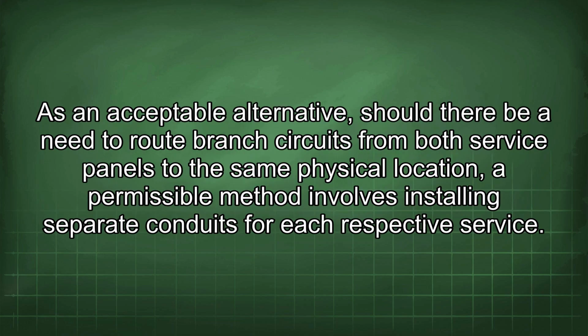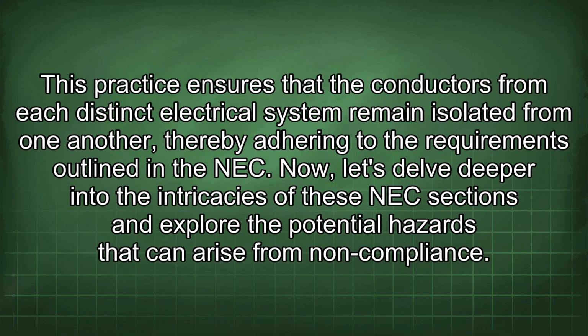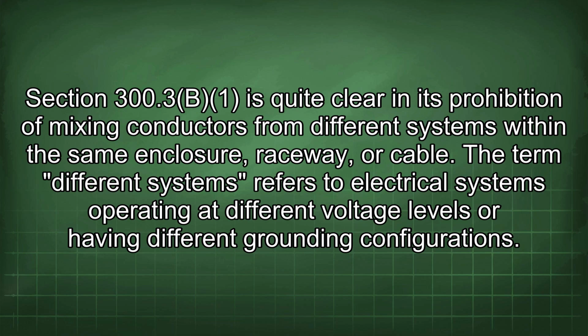As an acceptable alternative, should there be a need to route branch circuits from both service panels to the same physical location, a permissible method involves installing separate conduits for each respective service. This practice ensures that the conductors from each distinct electrical system remain isolated from one another, thereby adhering to the requirements outlined in the NEC. Now let's delve deeper into the intricacies of these NEC sections and explore the potential hazards that can arise from non-compliance. Section 300.3(B)(1) is quite clear in its prohibition of mixing conductors from different systems within the same enclosure, raceway, or cable.